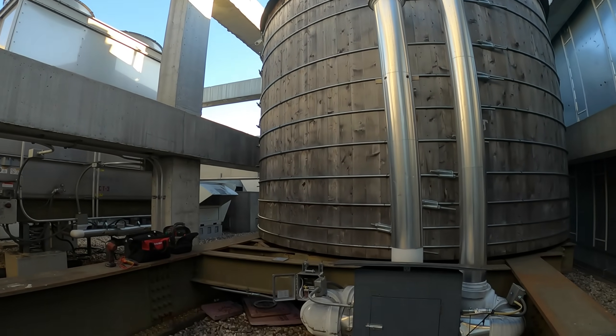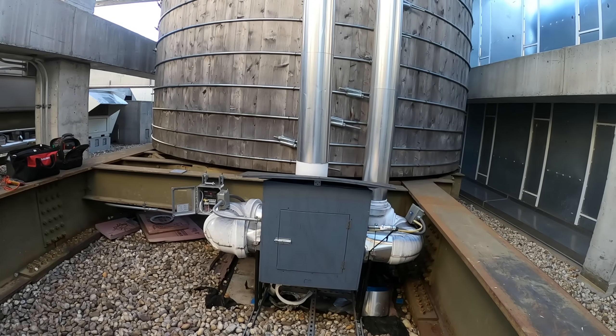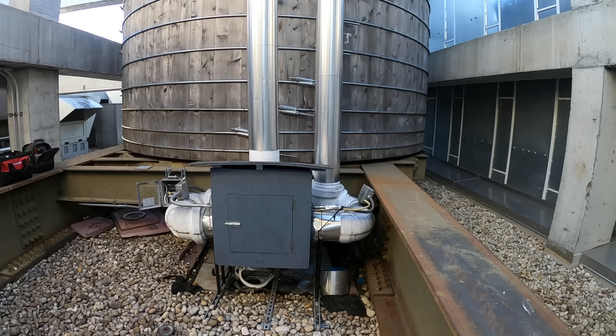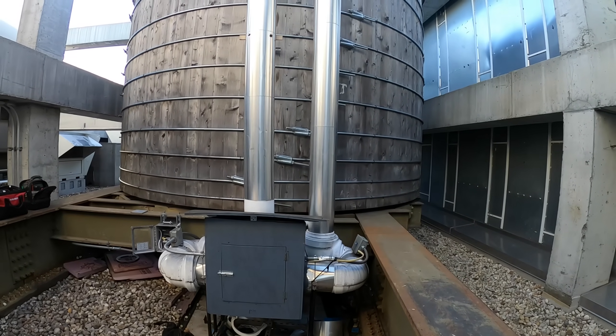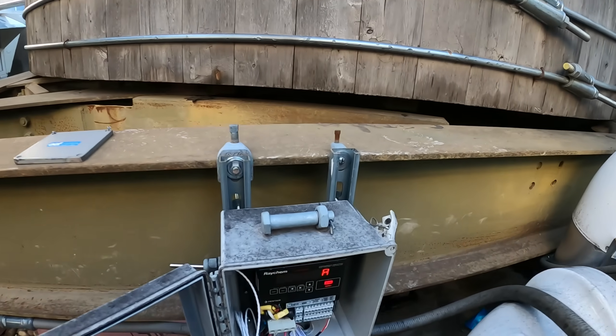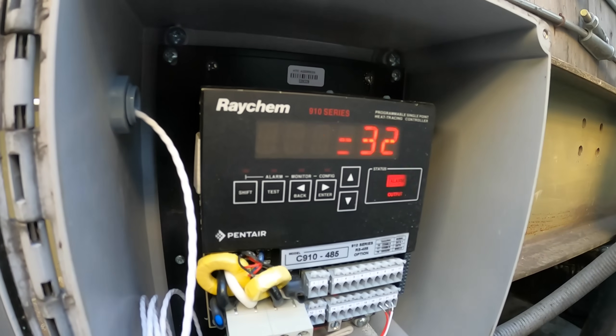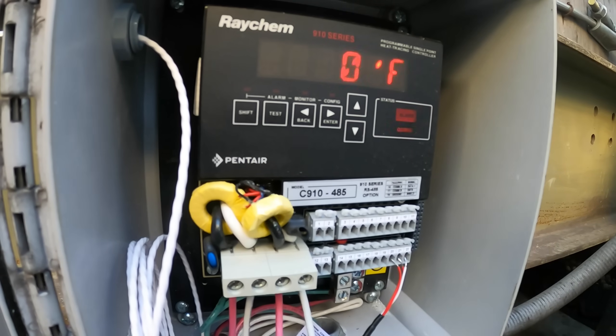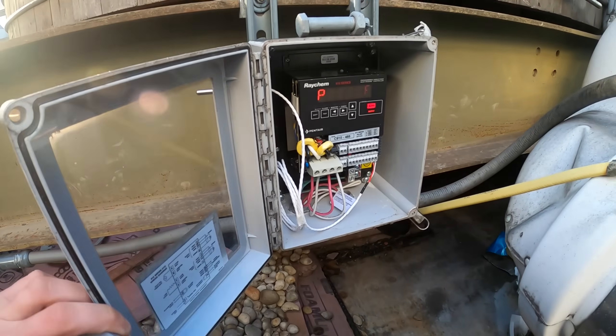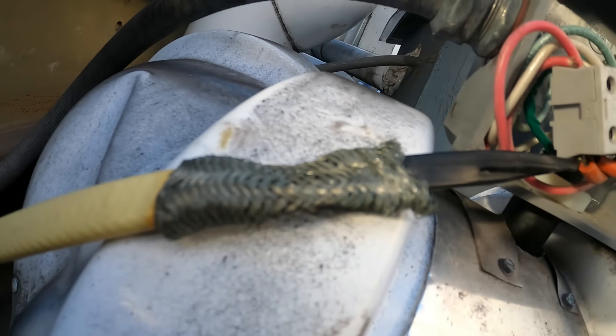I do a lot of work in this building and they asked if I could help. They want us to check the heat tracing system for this water tank — it's below 30 degrees out and they don't want any pipes bursting. They have this interesting controller made by a company called Raychem, the 910 series, model C910-485. I just opened up this little waterproof enclosure and took the cover off, and this wire was sticking out just like that.